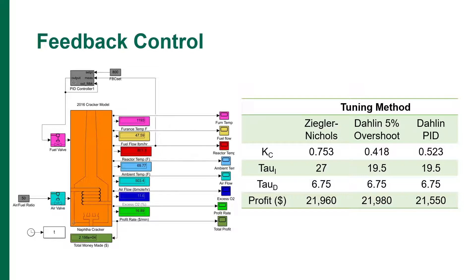Among other variables, the reactor temperature measurement is dependent on the amount of fuel fed to the furnace. So this measurement is compared to a set point of 800 degrees Fahrenheit, which then results in the controller manipulating the fuel valve, which is normally 50% open.